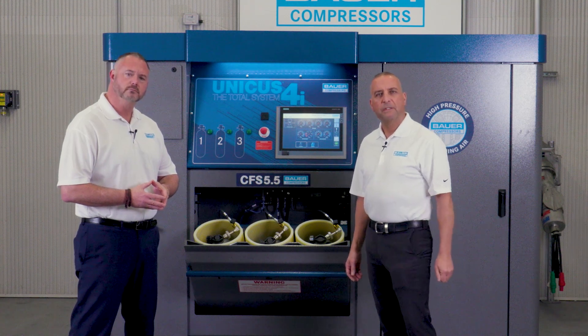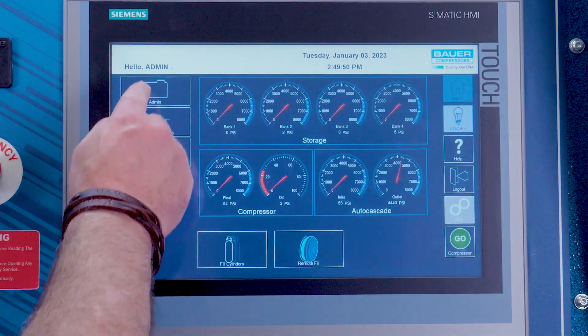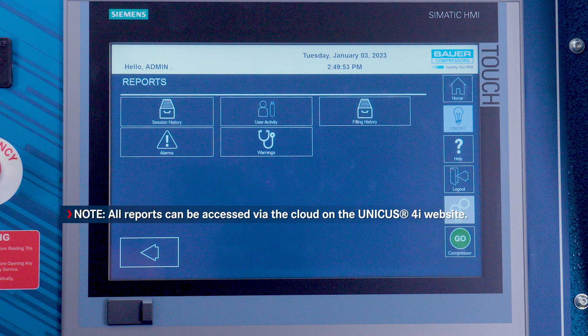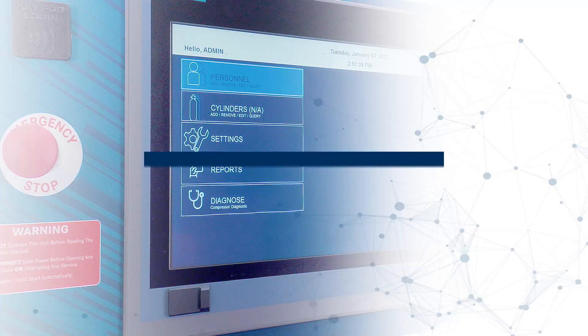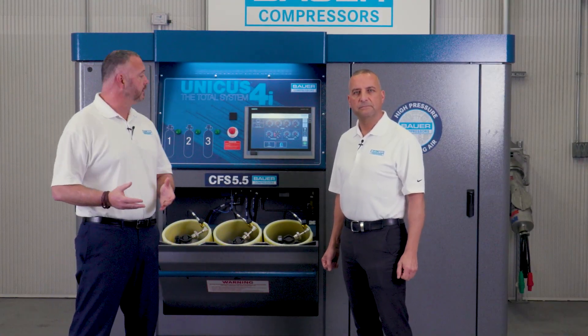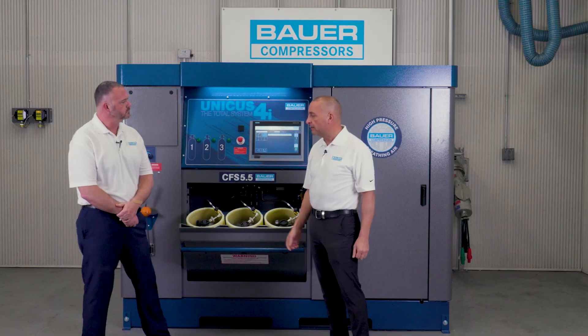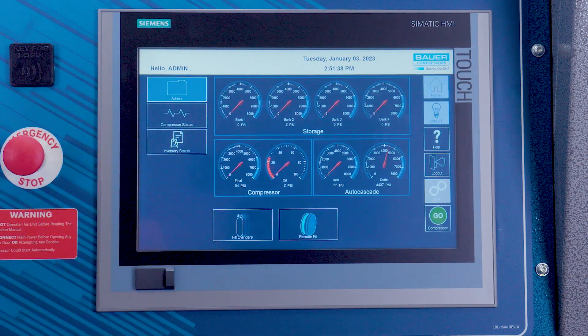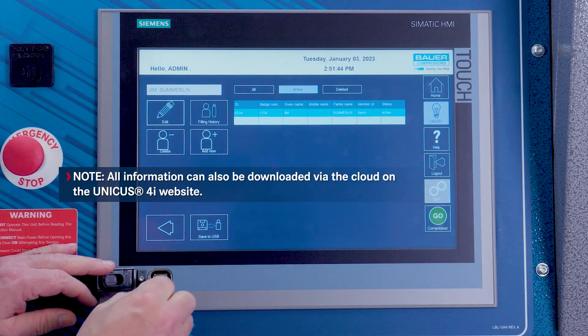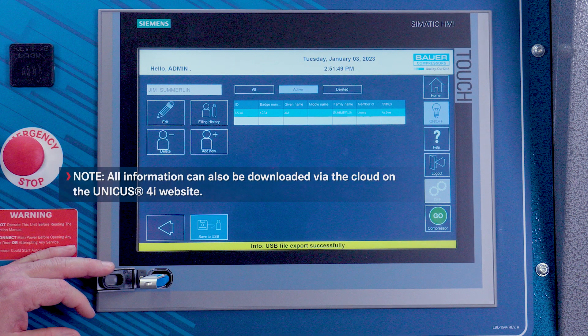Let's talk about accessing reports. Each UNICUS 4i has a minimum of one admin user. The admin user can access most screens; however, the setting configuration related screens are only accessible by Bauer personnel. To access reports, click the reports icon, then choose what type of reports as needed — for example, select reports, then alarms, then all. To download reports onto a flash drive, plug an empty USB drive into the USB port located at the left corner of the HMI panel. On the home screen, tap the admin icon. In the admin menu, tap the personnel icon. In the personnel menu, tap the save to USB icon once. This will automatically save your user data to the USB flash drive. Once the data is downloaded, a message saying 'USB file export successful' will pop up below the screen.